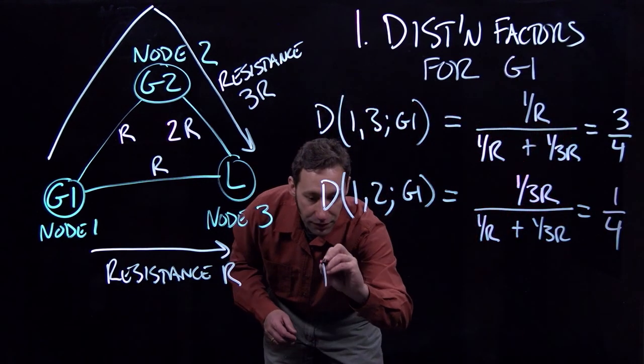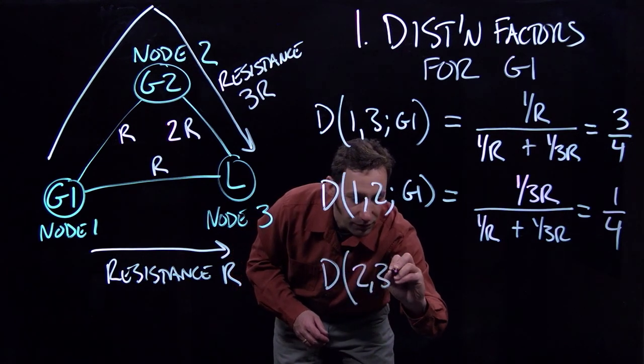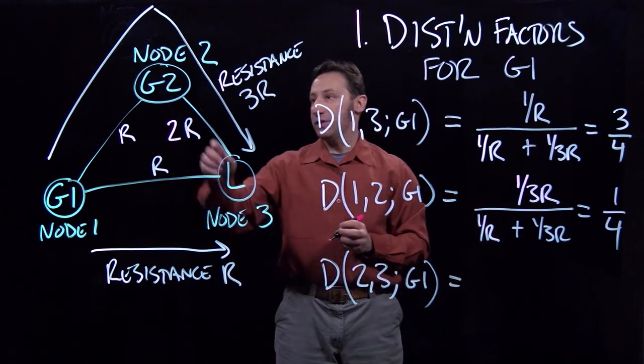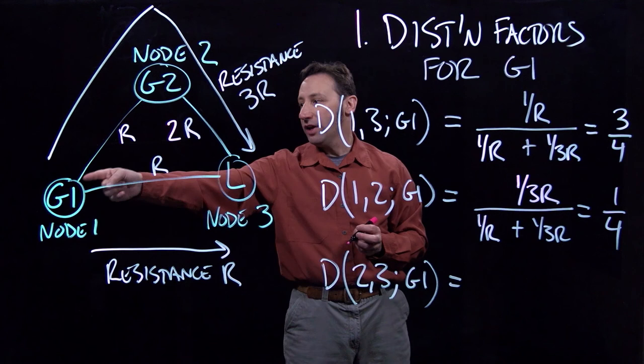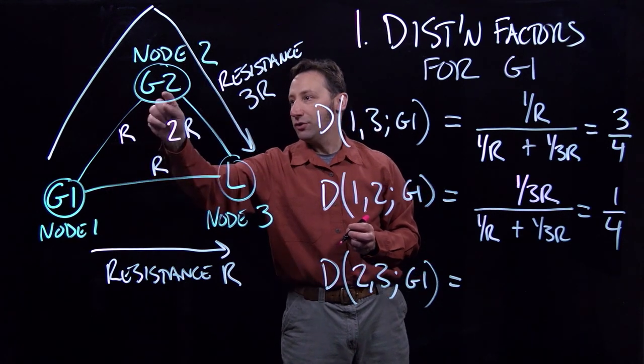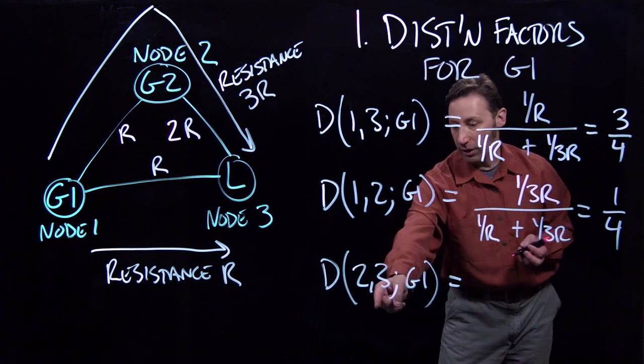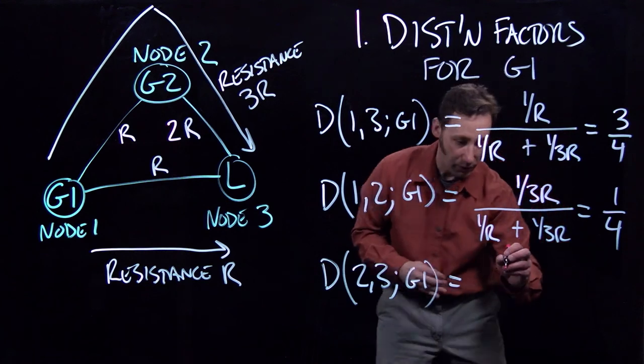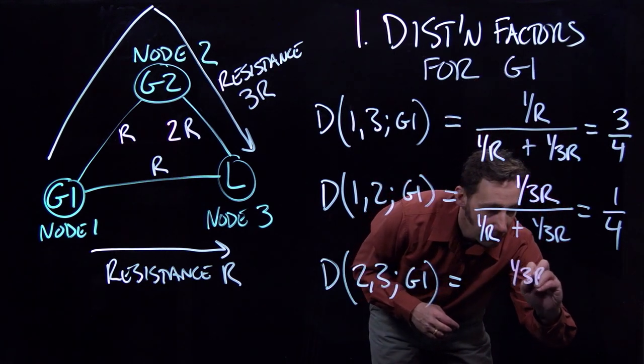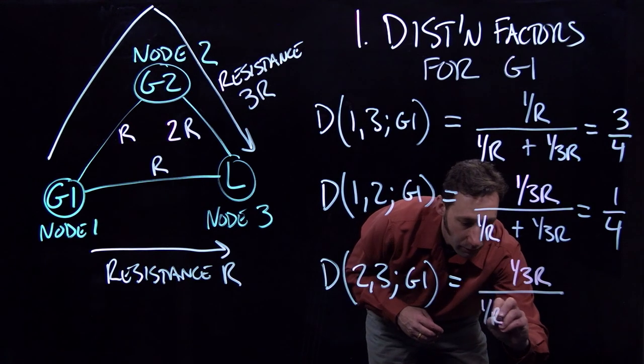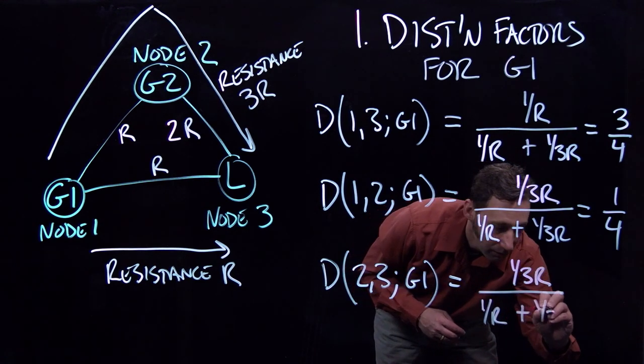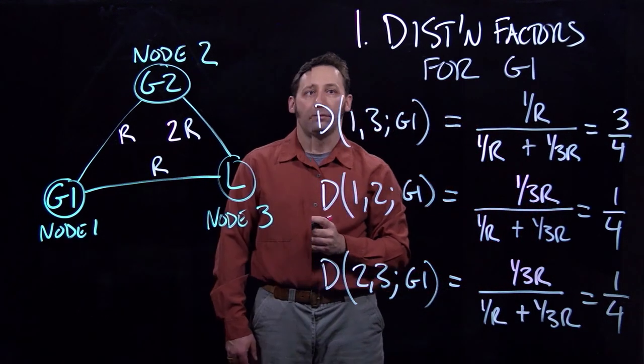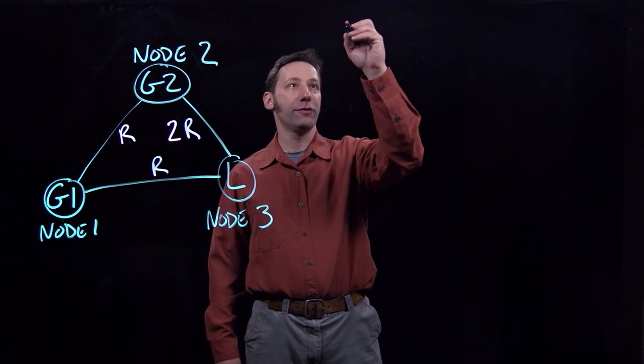Last, we're going to do the distribution factor of line 2 to 3 for G1. Because line 2 to 3 is on that same indirect path as line 1 to 2, we're going to have the same distribution factor on line 2-3 for G1 as on line 1-2 for G1. So we have 1 over 3R divided by 1 over R plus 1 over 3R, and we get 1 quarter.